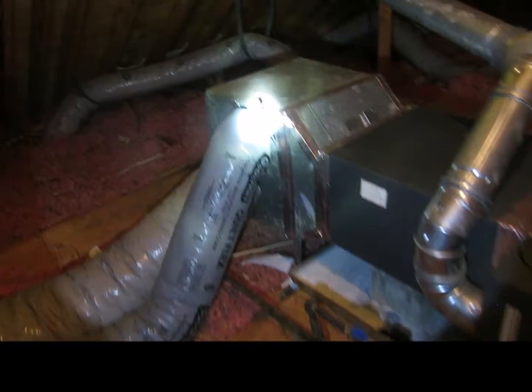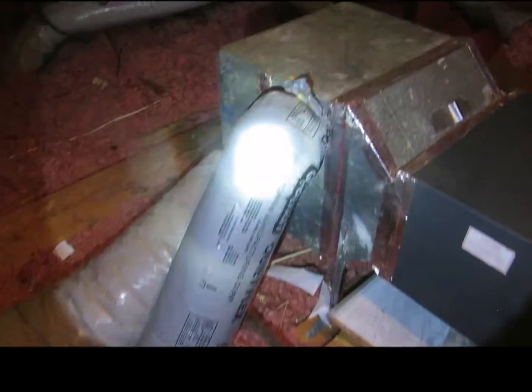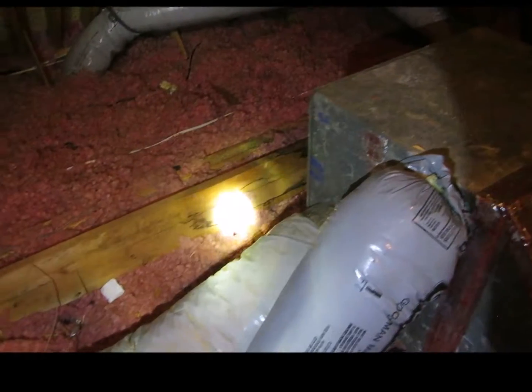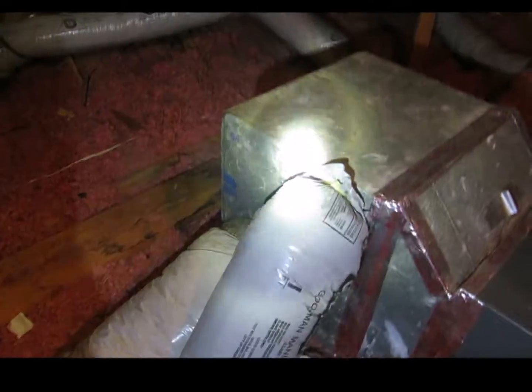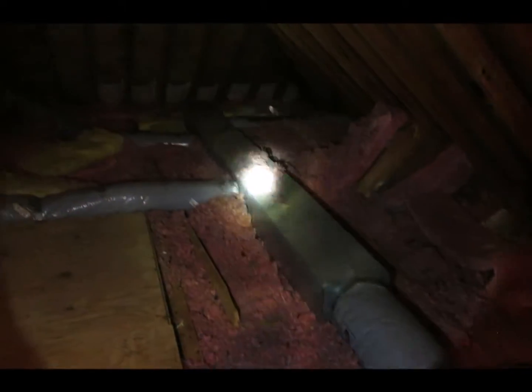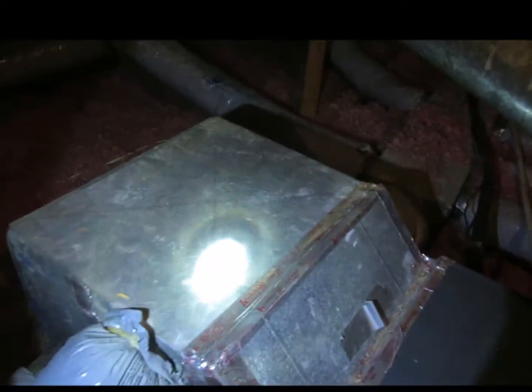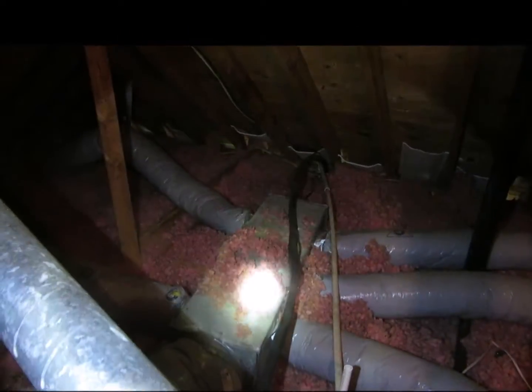Because these air ducts are not sealed and they've been open to the fiberglass, pollen, and the insects of the attic, I recommend that the ducts be cleaned and the metal boxes with their internal insulation be resurfaced. We have 3 of those. And then of course the ducts be air sealed.